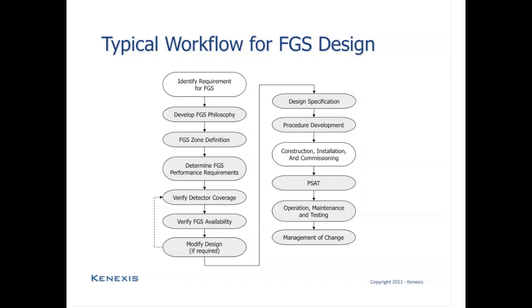After all of the zones have been defined, we need to determine the performance requirements for that zone. So for each zone, we're going to set various requirements such as the safety availability of any FGS functions that have been defined for that zone. And also we're going to set the coverage requirements for the fire and gas detection arrays that are covering that zone. After the performance targets have been specified, we are going to verify that the requirements have been achieved.